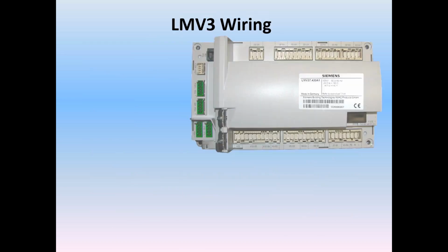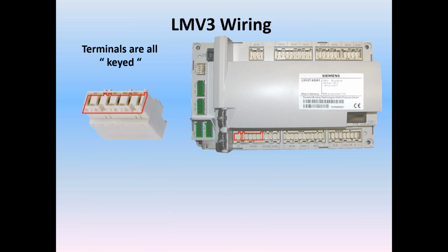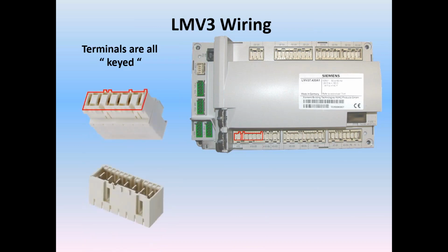LMV3, you see in front of you, the LMV3 chassis. The terminals are all keyed. That is, they have a specific shape so that the terminal will only fit in a specific socket that matches the key. So all the terminals that go on the LMV3 have keys. If you unplug them all, they can only be plugged back in a specific plug. It's the only one that will fit. This makes the wiring very easy and eliminates errors when servicing the LMV3.